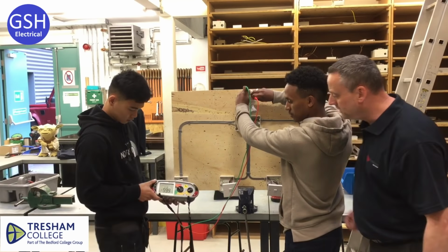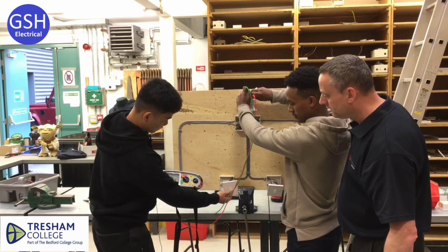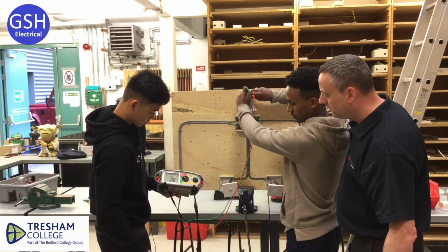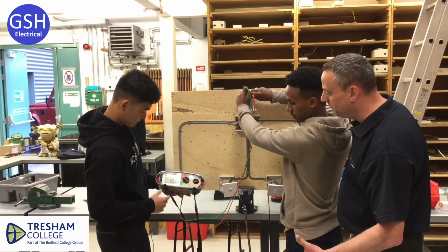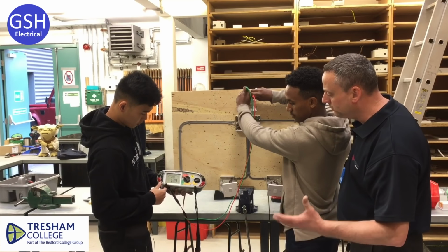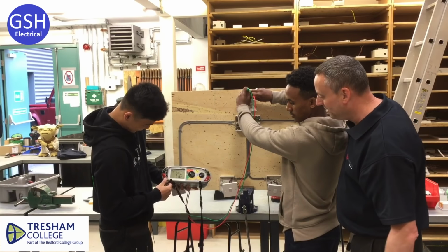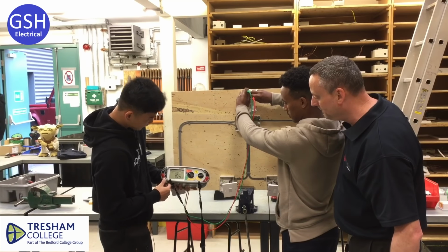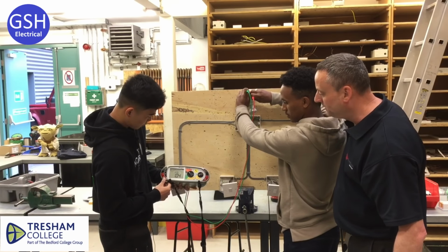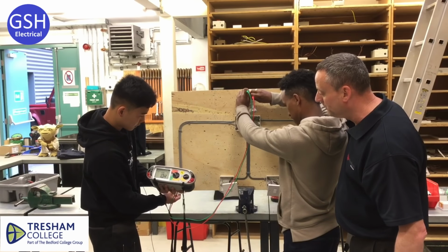Operate the first switch. The circuit's now gone off. Now we've got a slightly different reading, slightly higher, and we need to remember that. So we go again, and we've gone off. Got a considerably higher reading now, because we've got more parts of the switching circuit in. Abil's now jumping all over the place. Okay, let's just hold that firmly for you. Push nice and firmly, Abil. So we've got 1.04, excellent. That's the one at the moment we're going to remember.